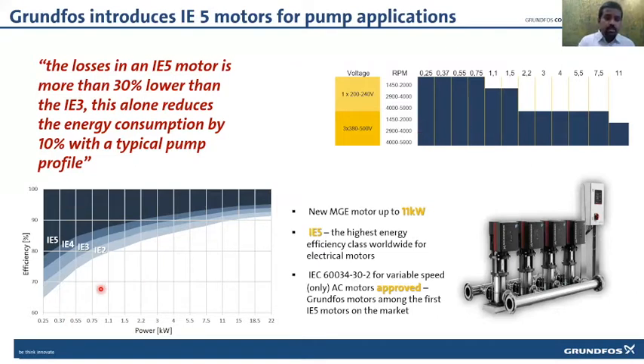And the efficiency comparison, this is on full load comparison, IE2, IE3, IE4, and IE5. So we can see IE3 at full load can go up to 70%, and it can maximum go up to 92 to 93%. Whereas with IE5, for any ranges, we can sustain at 80%, and we can hit 95% at full load. But the interesting factor is part load. Still, we have more savings when compared to conventional induction motors. We have seen applications where we can save up to an average of 15 to 20% or 25%, especially at part load and lean load conditions. And this is on the product side.